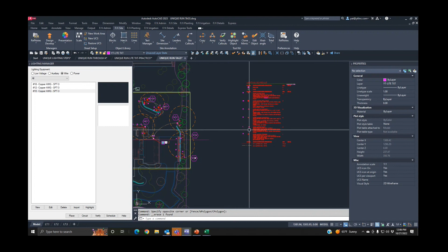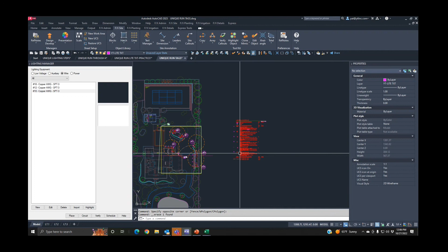We'll rerun the schedule at this point to update all of our wires and get our taps on the lighting schedule. And we will also always include that Excel spreadsheet on the file so that our installers know what our amp rating is on which wires, and they can double check that in the field.